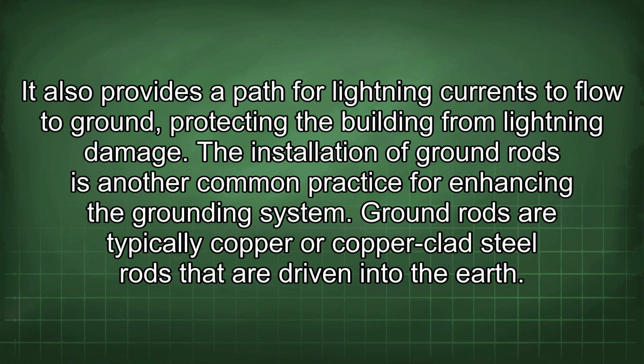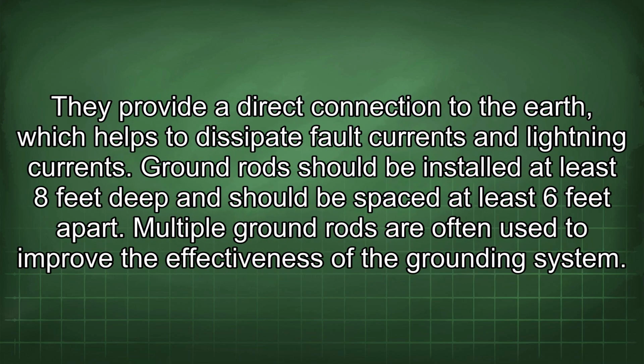The installation of ground rods is another common practice for enhancing the grounding system. Ground rods are typically copper or copper-clad steel rods that are driven into the earth. They provide a direct connection to the earth, which helps to dissipate fault currents and lightning currents. Ground rods should be installed at least 8 feet deep and should be spaced at least 6 feet apart. Multiple ground rods are often used to improve the effectiveness of the grounding system.